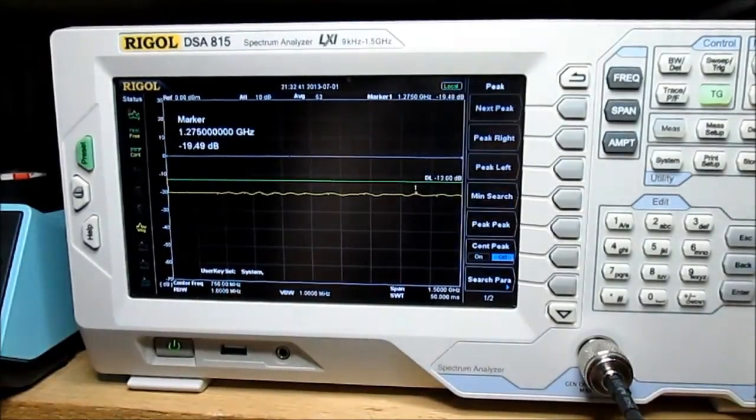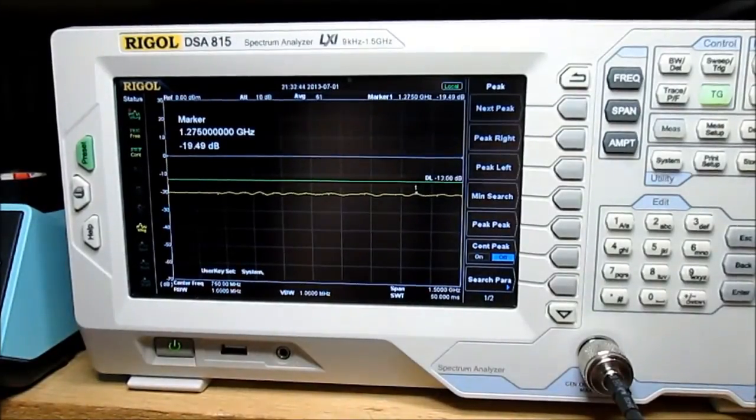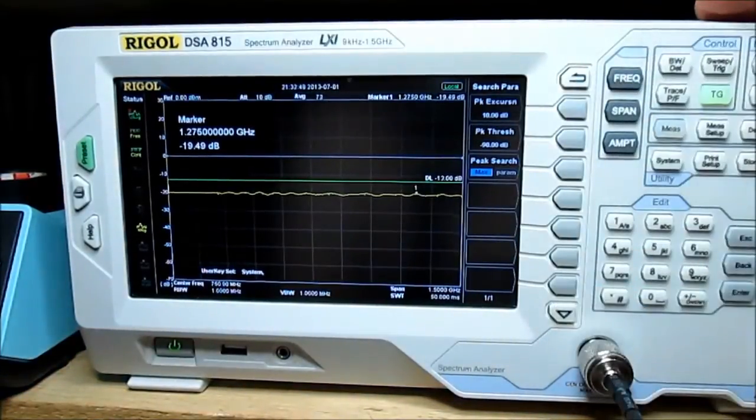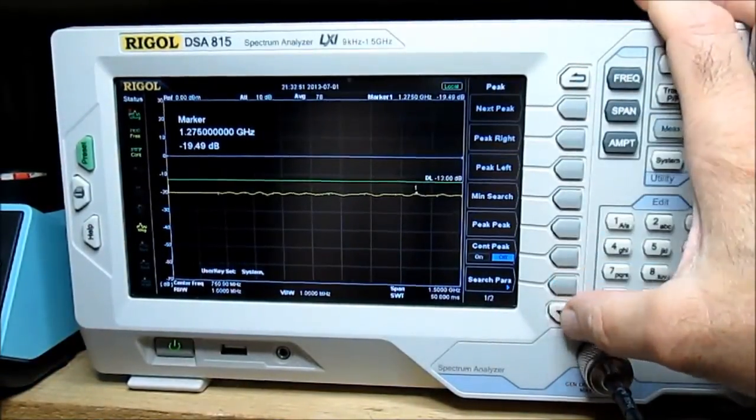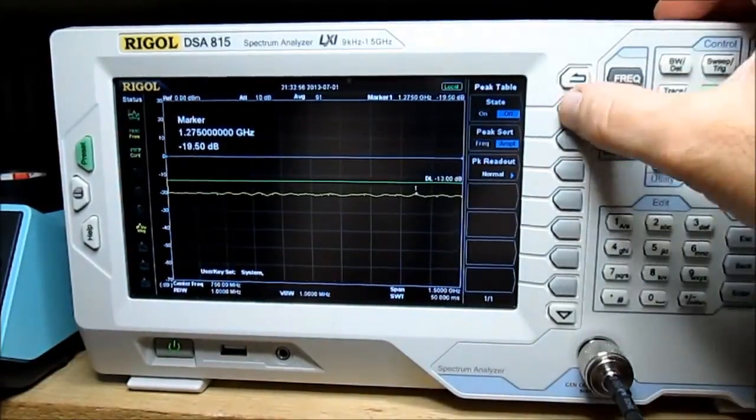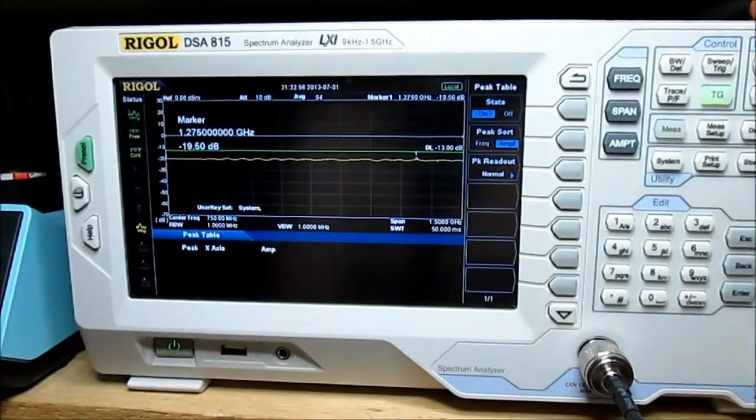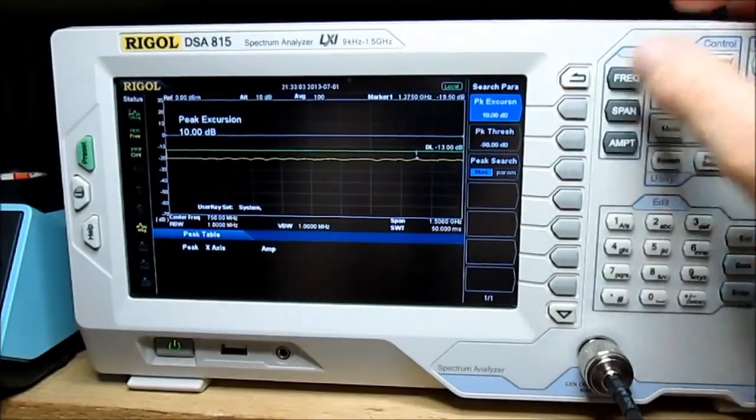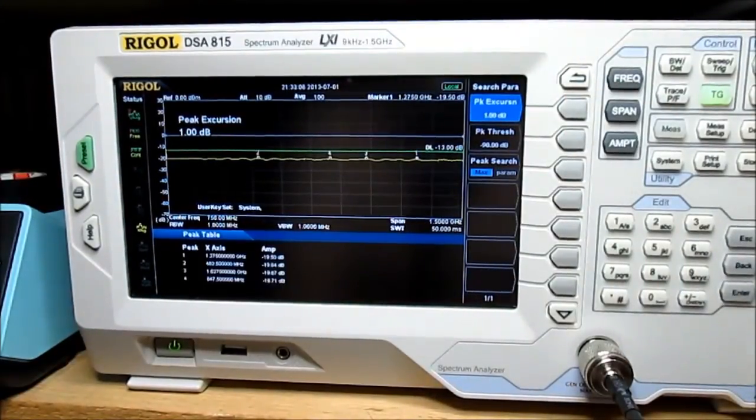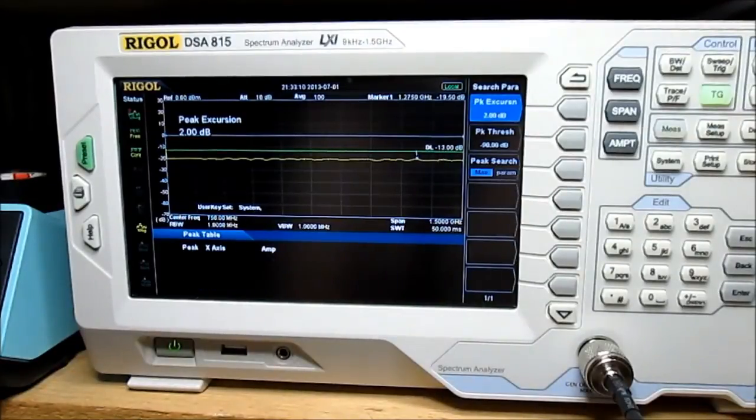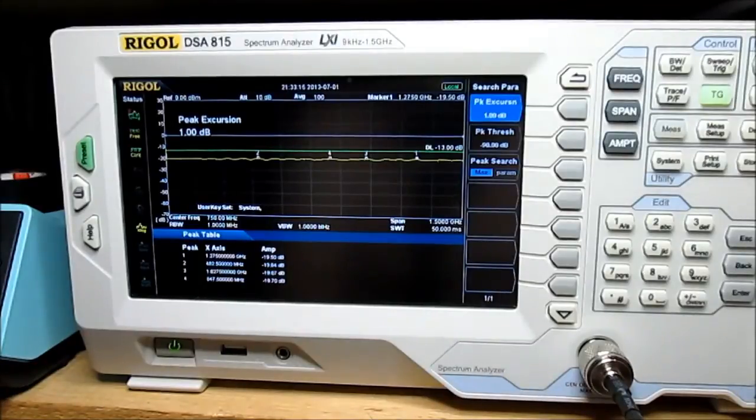But let me turn on a peak and see, search parameters. Well let's not do the threshold yet, let's go back to peak. And go down one, turn on the peak table, peak sort, do it on amplitude. Turn it on. And then go back to peak, to search parameters, excursion, and lower this down.